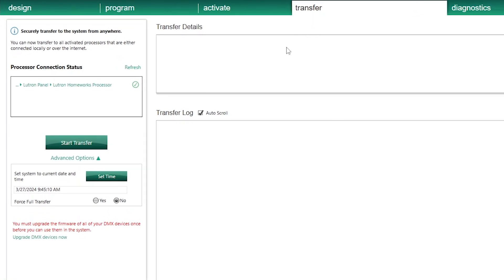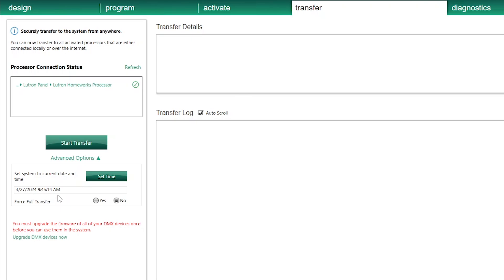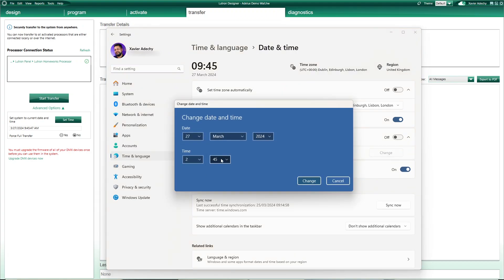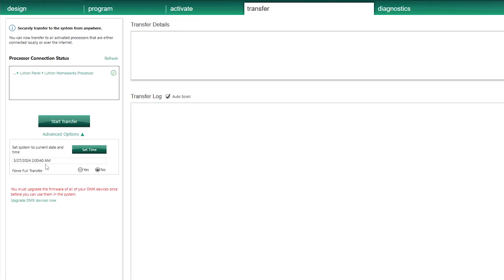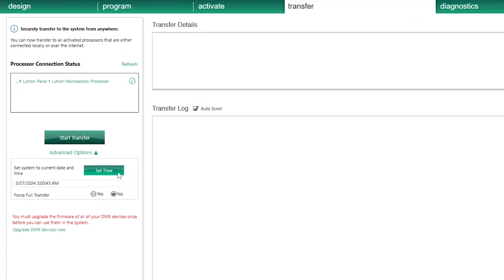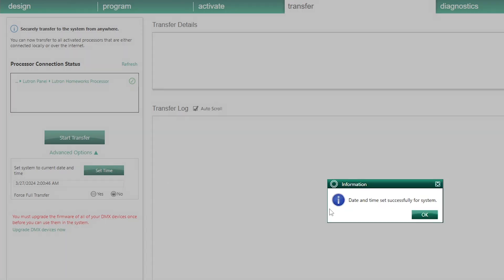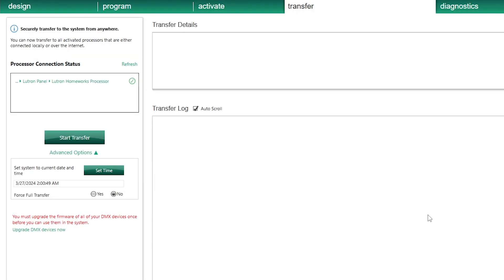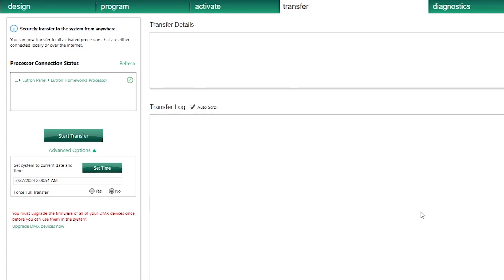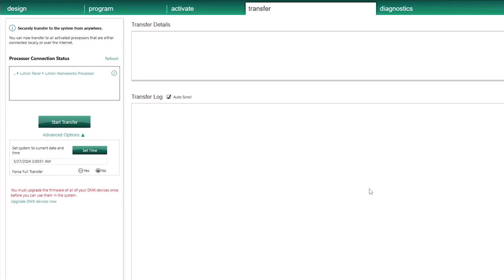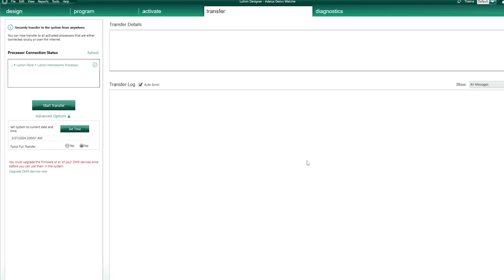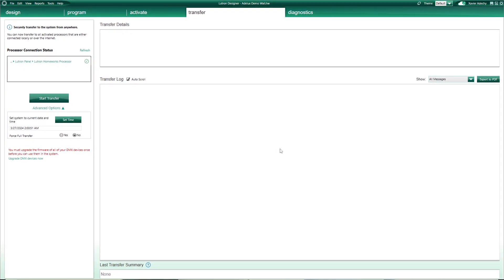Now, if I go to the Transfer tab on my Lutron Designer software, I can see the current time on my processor. To change the time, one way is to go to my computer date and time settings and change the time to, let's say, 2 AM. Back on the Transfer tab, as soon as I click on the Set Time button, my processor time updates to my computer time — and no need for a transfer. One important thing though: when you finish testing your conditional programming, always remember to reset your Homeworks processor to the current time and date before you leave the site.